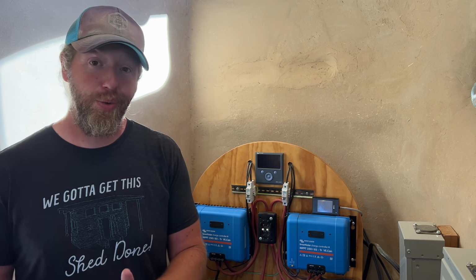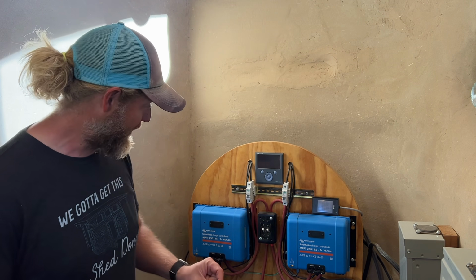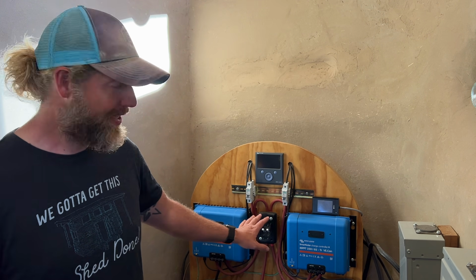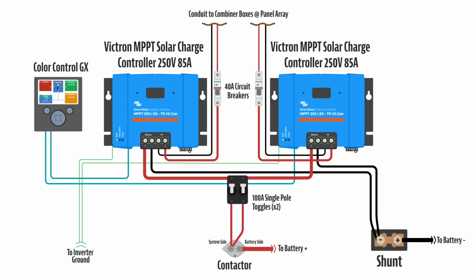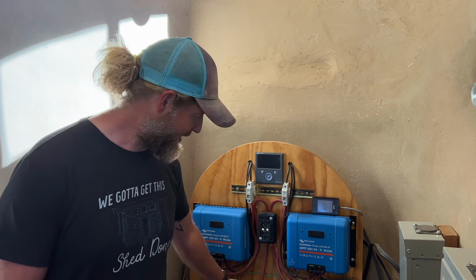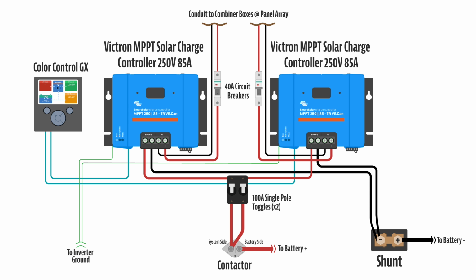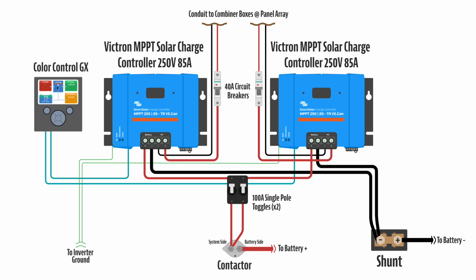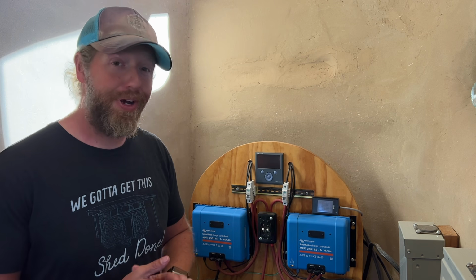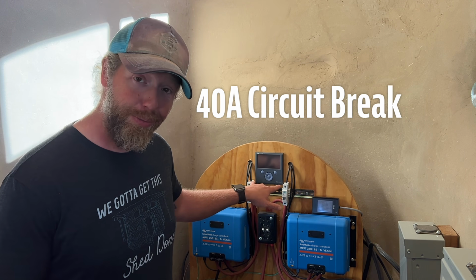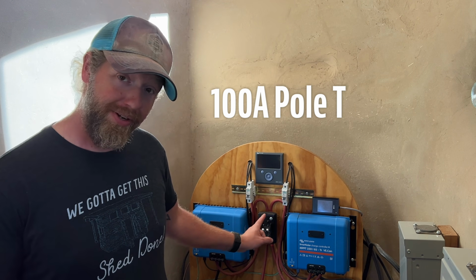Out of that, we go through another set of circuit breakers right here, these are 100 amps each, and the positive power from the solar charge controllers runs through here and down to the system side of the contactor. You also run 2-gauge wire from the negative side of both solar charge controllers all the way down to your shunt. For reference, these are 40 amp circuit breakers and these are 100 amp circuit breakers.